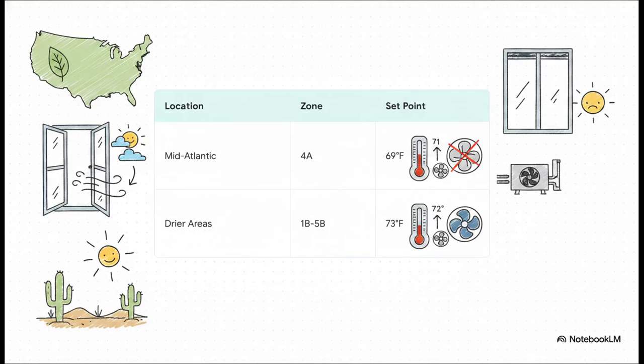So how does this actually play out in the real world? Well, optimal set points completely depend on where you are on the map. Take a moderate climate like the US Mid-Atlantic, climate zone 4A, for example. The limit there might be set at 69 degrees. If it's 68 degrees outside, the system kicks on and brings in that free cooling. But the second it hits 71, the system realizes, nope, too warm, shuts the outdoor dampers, and turns the mechanical AC back on. Now, if you're in a much drier area, say zones 1B through 5B, you can actually afford to push that limit up to 73 degrees.